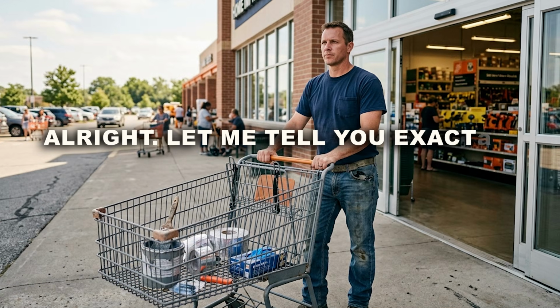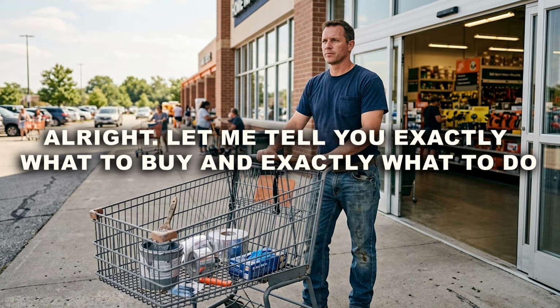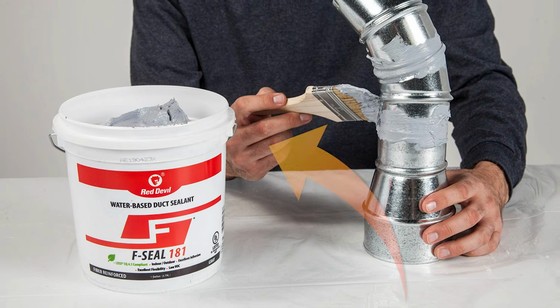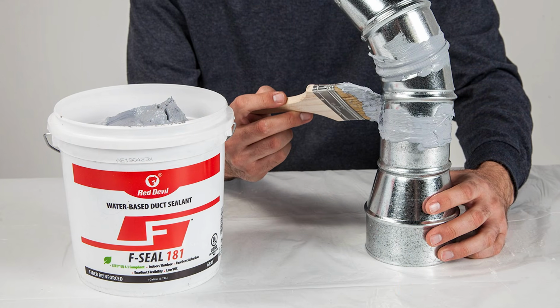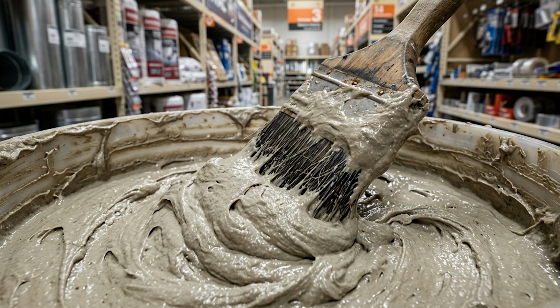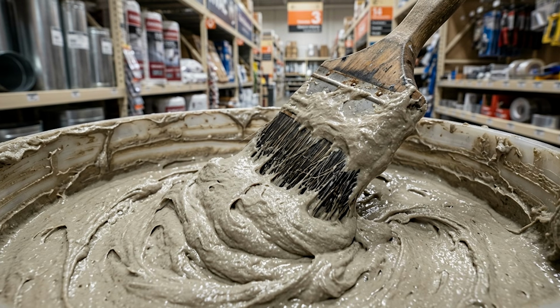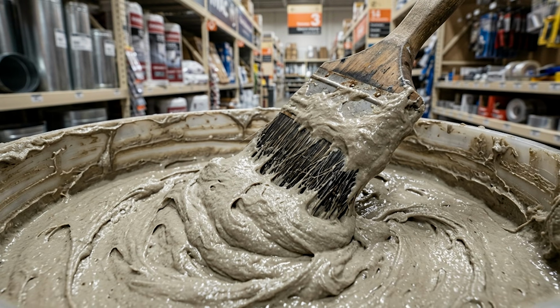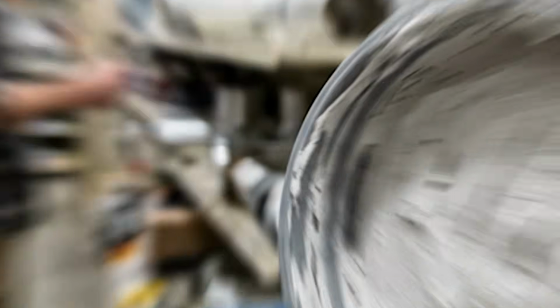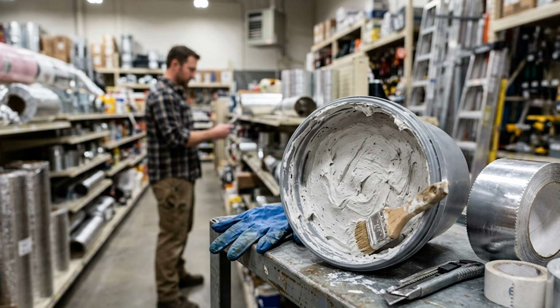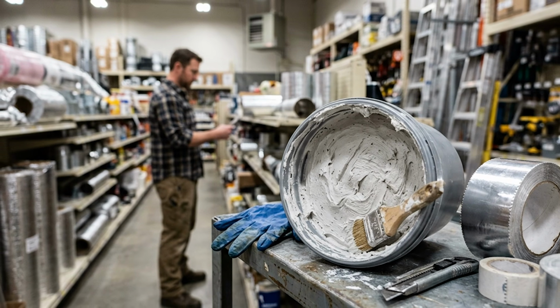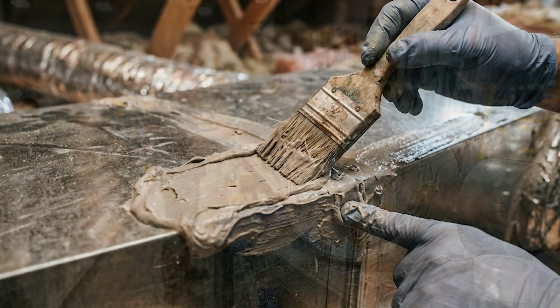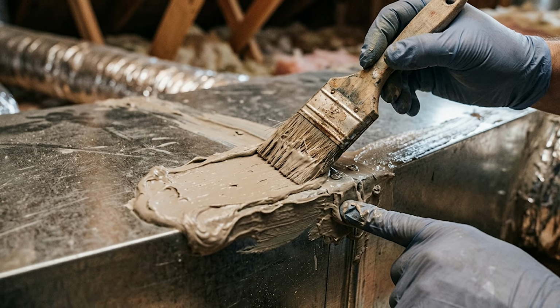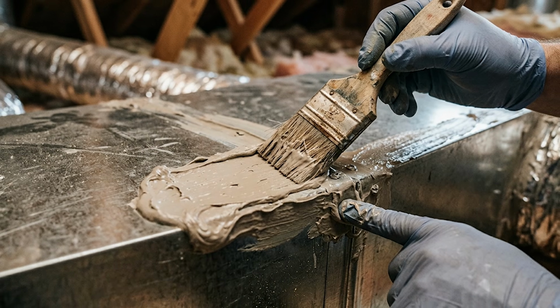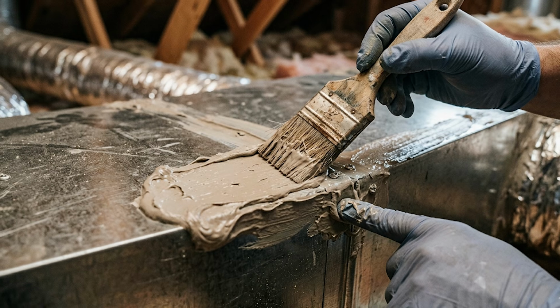All right, let me tell you exactly what to buy and exactly what to do. The product is called Mastic Duct Sealant, and this is what it actually is. It is a water-based, flexible, adhesive compound specifically engineered for sealing HVAC ductwork. It looks like thick peanut butter. It goes on with a cheap paintbrush or even with a gloved finger. It stays permanently flexible after it cures, which matters because your ducts expand and contract with temperature changes every single day.